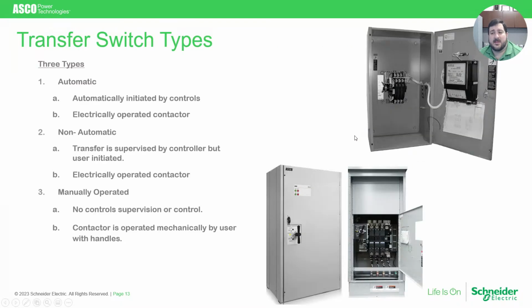There's a couple different types of transfer switches. We have automatic transfer switches, which are the most common and most popular that you'll hear us talk about. These are transfer switches that are automatically initiated by controls and a controller inside the equipment. It will detect the power failure and initiate the emergency source and transfer to it completely automatically. Does not require a user. And the transfer is electrically operated, meaning the switch contactor electrically will operate the solenoid mechanism, switching the contactor from being connected to one source to the other.